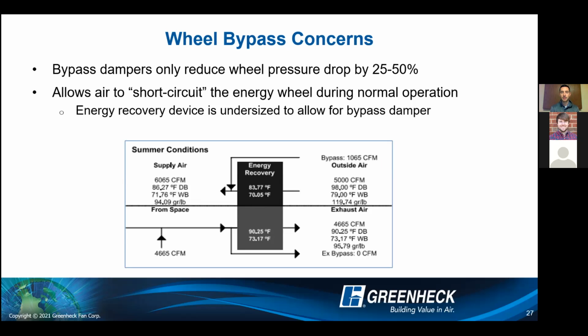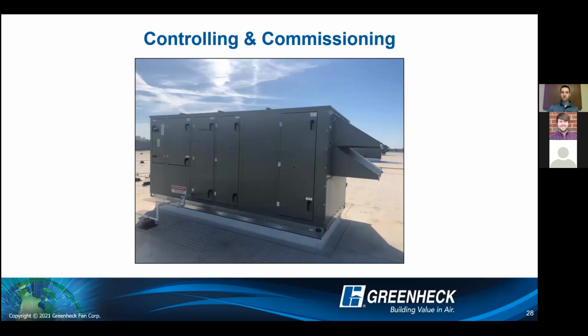So even if they're not in economizer, they're only moving 5,000 CFM through the energy wheel and bypassing that other really high temperature, really high humidity outdoor air around. So instead of all of that air leaving the energy wheel at this 83 degrees that you see on there, now it's actually mixing prior to the cooling coil at 86 degree dry bulb, 71 degree wet bulb. So your cooling has to be increased downstream. Again, so during normal operation, that's going to reduce the effectiveness. It might put you in harm of not meeting that 50% effectiveness from a code standpoint. So always things you want to consider when looking at wheel bypass.